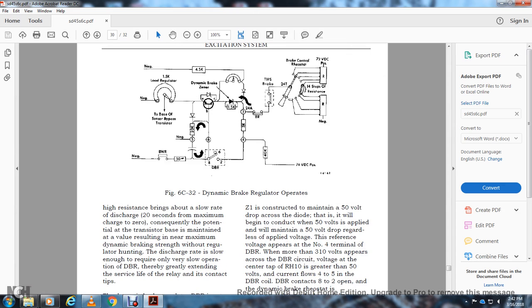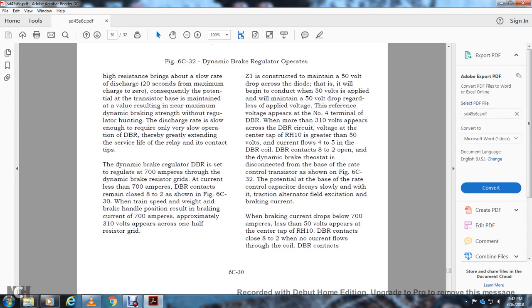High resistance brings, so that we just look at the different paths it could take. High resistance brings about a slower discharge, so consequently the potential of the transistor base is maintained at the value resulting in near maximum dynamic braking strength without regulation. However, the discharge rate is slow enough to require slow operation of the dynamic braking relay, greatly extending the service life of the relay contact.